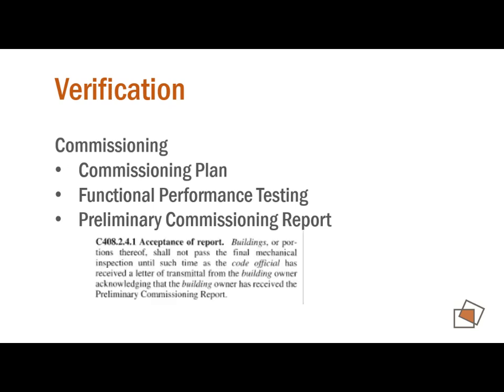Then the code requires acceptance of the report. It says buildings or a portion thereof shall not pass the final mechanical inspection until such time as the code official has received a letter of transmittal from the building owner acknowledging that the building owner has received a preliminary commissioning report. So until you've done functional performance testing and got your report submitted to the owner, you can't get your final mechanical.